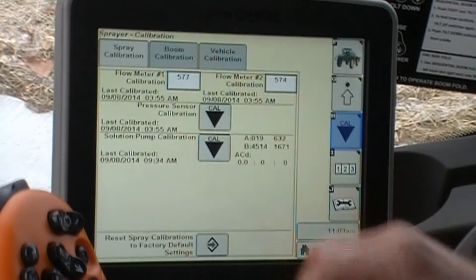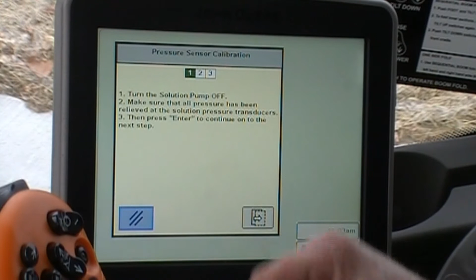In this option, a high flow option, we have a second flow meter. Below that, you have a pressure sensor calibration. When we go in there, we simply make sure everything is off, there's no pressure in the system, and we are zeroing out the pressure sensor.